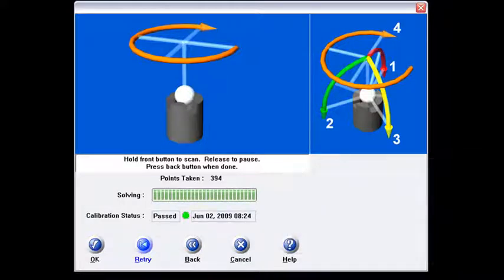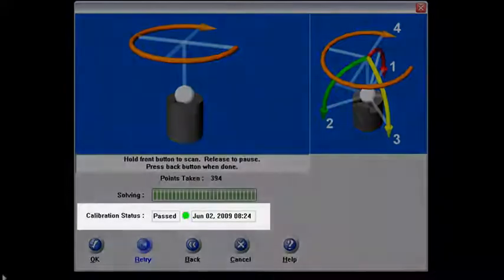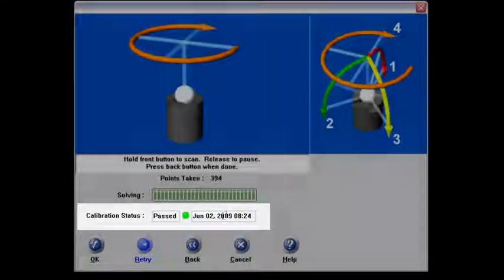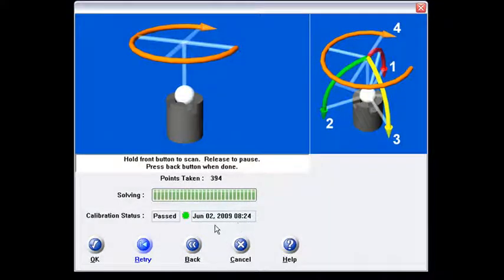Then Faro goes through and it solves for the best fit point in the center of that cone. As you can see on my screen here the calibration status is passed and it's got today's date on it at 8:24 in the morning. So I'm going to say okay to that.